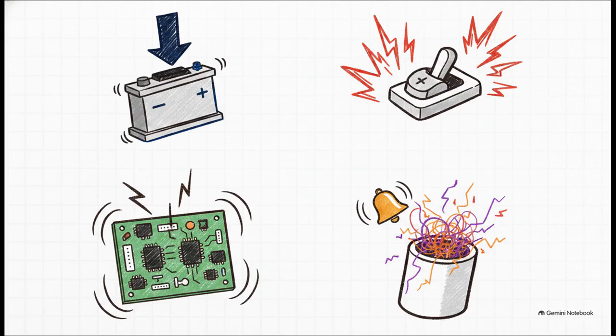Third, mechanical harmonics. You can think of this as an invisible earthquake. Frequencies between 100 and 1000 Hertz from the motor can actually match the natural resonance of the circuit board, shaking the solder joints until they form microcracks. And fourth, desat, or desaturation interference. That same crazy electrical noise we just talked about can accidentally charge up safety capacitors, tricking the whole system into thinking there's a short circuit when there really isn't one, which leads to a totally unexpected loss of power.